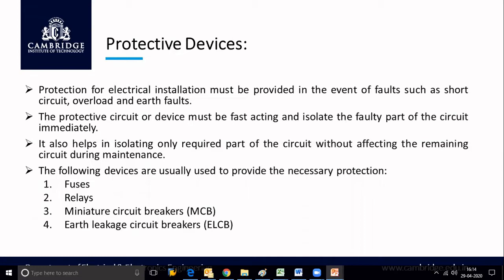It should act very fast and also it should isolate the faulty part of the circuit. It also helps in isolating only required part of the circuit without affecting the remaining circuit during maintenance. Now, the most commonly used protective devices for the necessary protection are fuses, relays, miniature circuit breakers, shortly we call them as MCBs, and earth leakage circuit breakers, that is ELCBs. For our syllabus, in this video, we are going to discuss about fuses and miniature circuit breakers, MCBs.